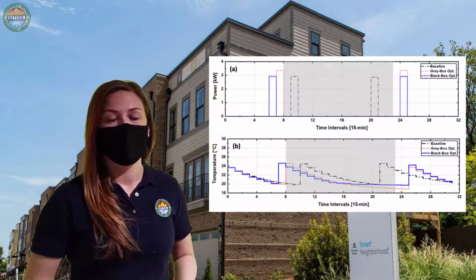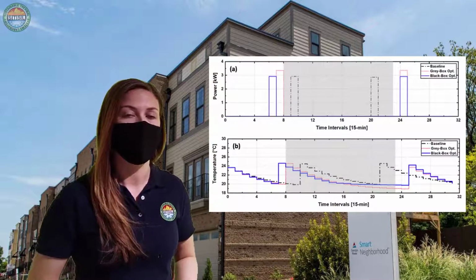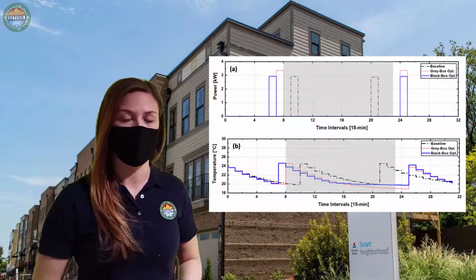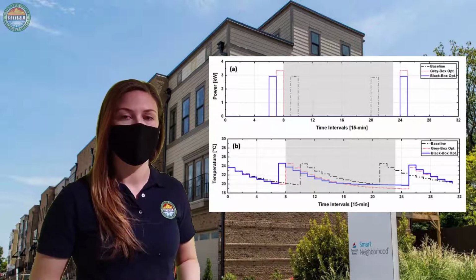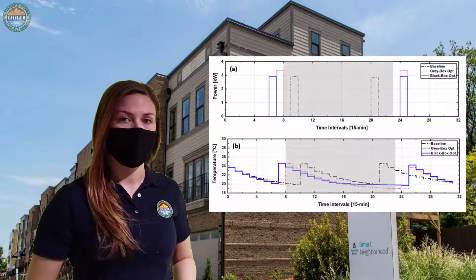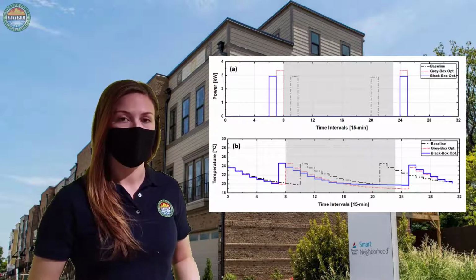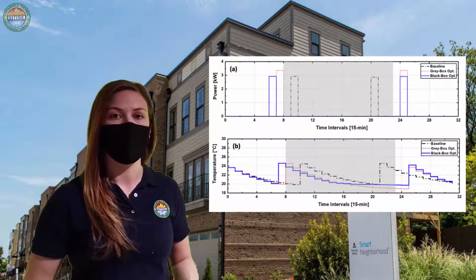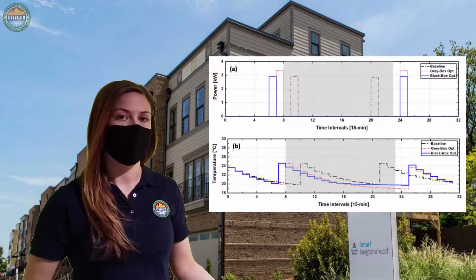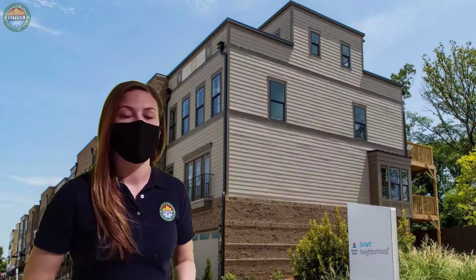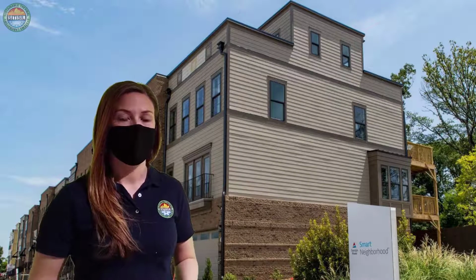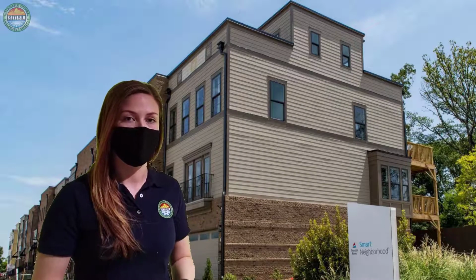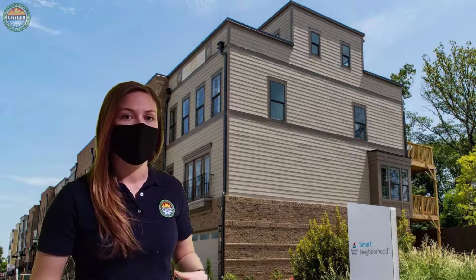For example, with the HVAC system in summer, we might use it to pre-cool the house below the typical set point by a couple degrees during the midday period when we have that excess PV generation, which would allow us to shift energy out of the peak demand period by reducing the HVAC electrical demand at that time. Because each of these houses is contributing a very small amount of energy to the load shifting, it's desirable to aggregate them at a regional level.